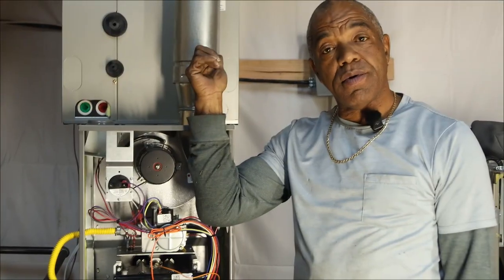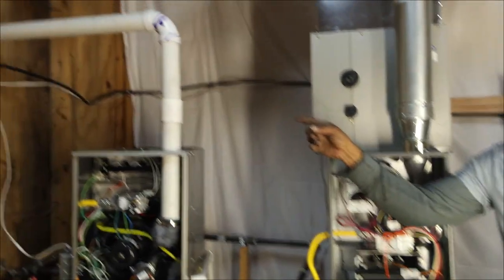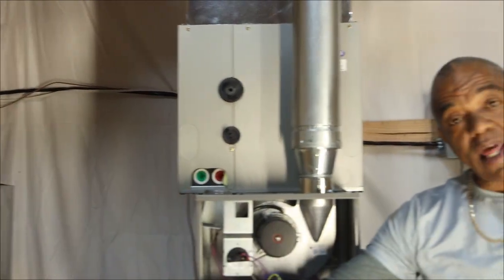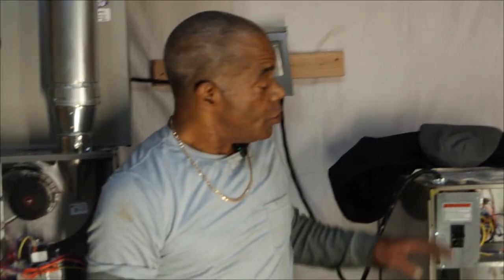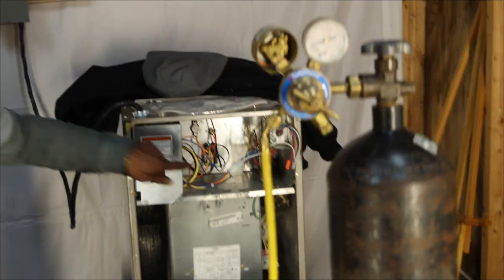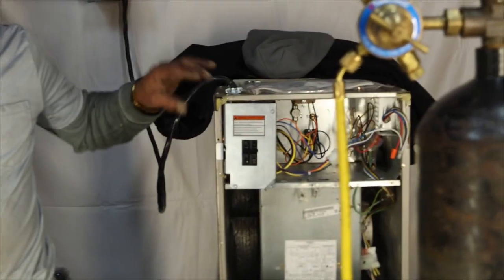This flue pipe is metal. That flue pipe is plastic, PVC. We're going to understand that 90 plus furnace and this 80 plus furnace. We're going to understand this heat pump along with its electric element and everything about each of these units. And just like I can diagnose a large volume of problems by phone, by simply asking some questions, you're going to be able to do that also, because when you know all the components in the system, you know what they do.